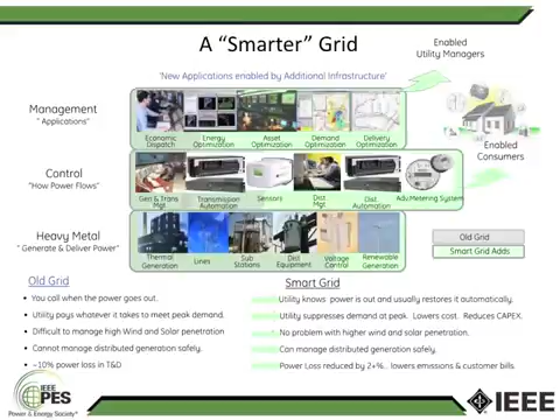So I mentioned residential rooftop solar PV. I wrote an article in Power Electronics magazine, the August 22nd, 2013 issue, after looking at the results that were experienced both in California and Arizona, where a distribution feeder had 35% penetration of the homes on that feeder with rooftop solar panels, and the impact that cloud and fog have on the distribution grid. So as an example, San Diego Gas and Electric, one of their feeders, the homes along the ocean had fog that blocked the sun's rays in the morning, and as that fog burned off, going from 0% to 100% sun, the voltage on the feeder would spike and then oscillate as the cloud cover went in and out.